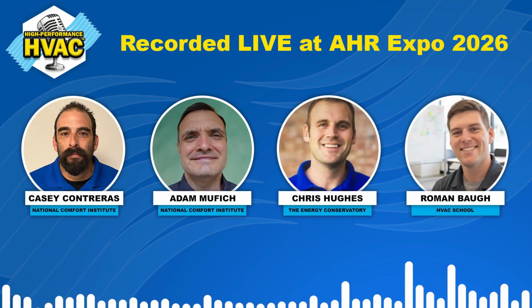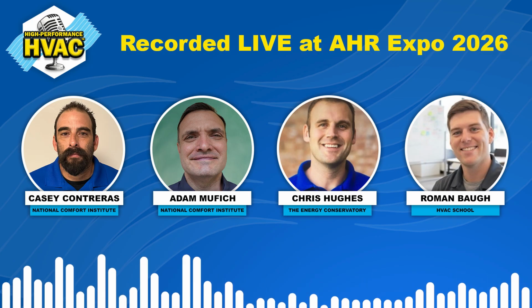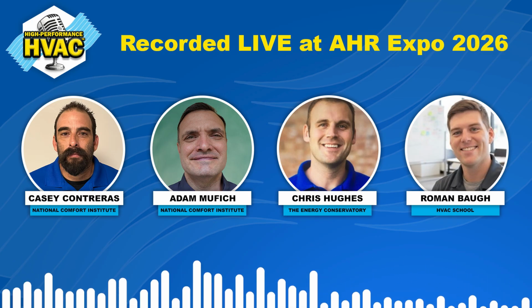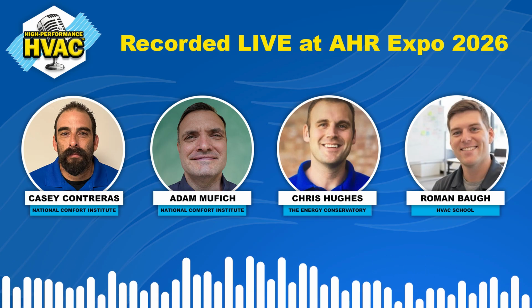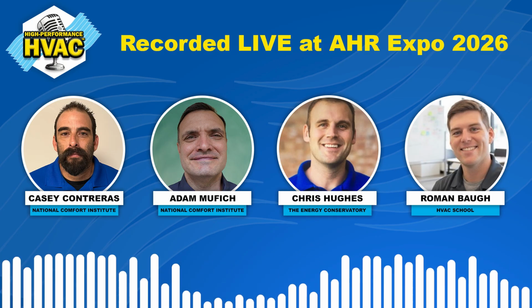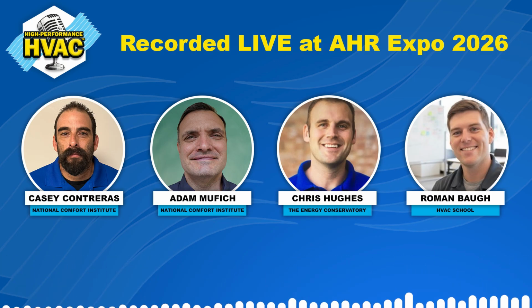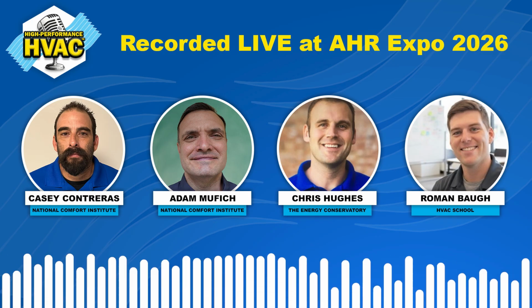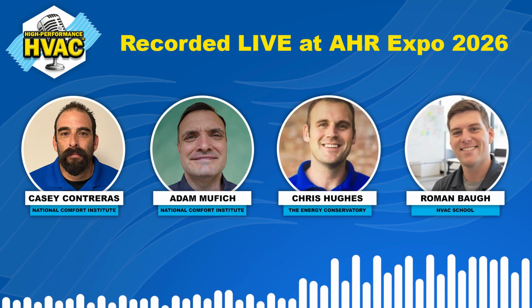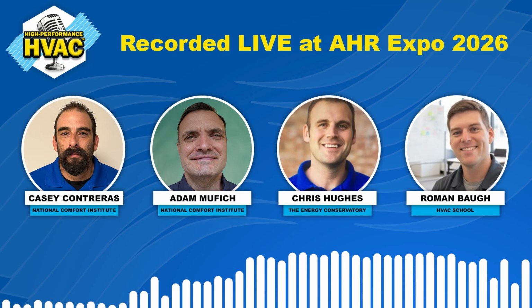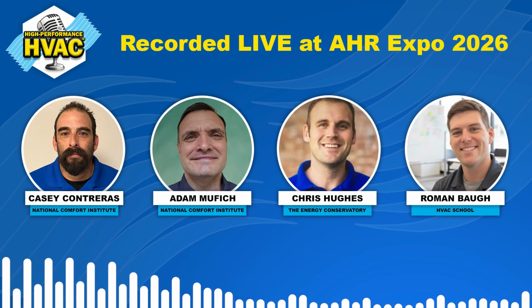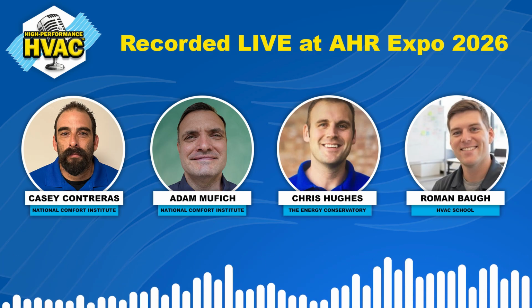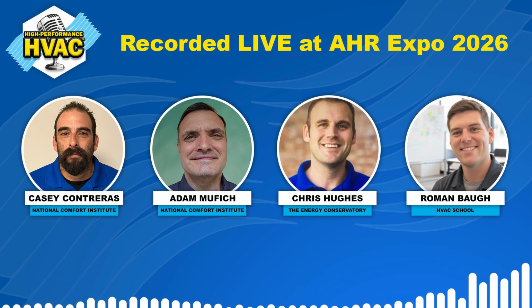Okay. Yeah, but you're also paying attention to something in residential we don't look at. Yeah, discharge superheat. So suction superheat, discharge superheat, system subcooling. And you kind of triangulate, which is super cool. What do you call it? The troubleshooting triangle. That's if I had a bell, I'd ring it. That's a trademark, right? Not yet. So can we hit that second one? I don't know if I'm super familiar with that.